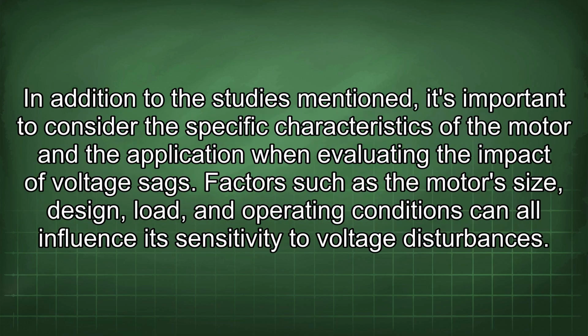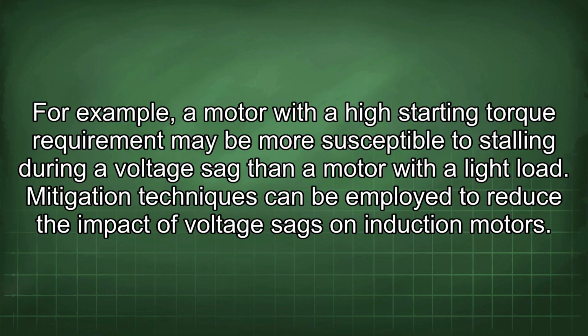In addition to the studies mentioned, it's important to consider the specific characteristics of the motor and the application when evaluating the impact of voltage sags. Factors such as the motor's size, design, load, and operating conditions can all influence its sensitivity to voltage disturbances. For example, a motor with a high starting torque requirement may be more susceptible to stalling during a voltage sag than a motor with a light load.